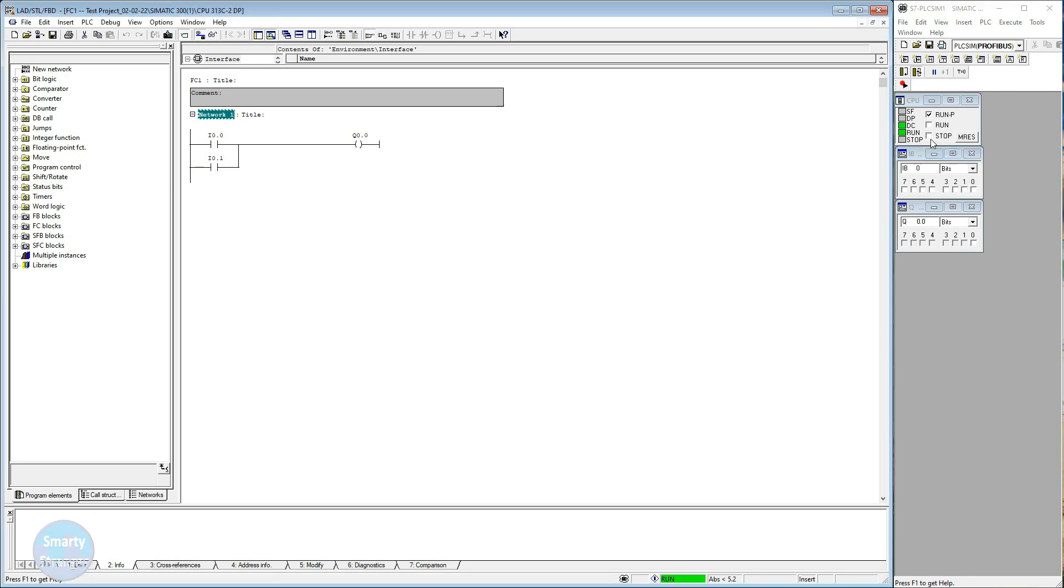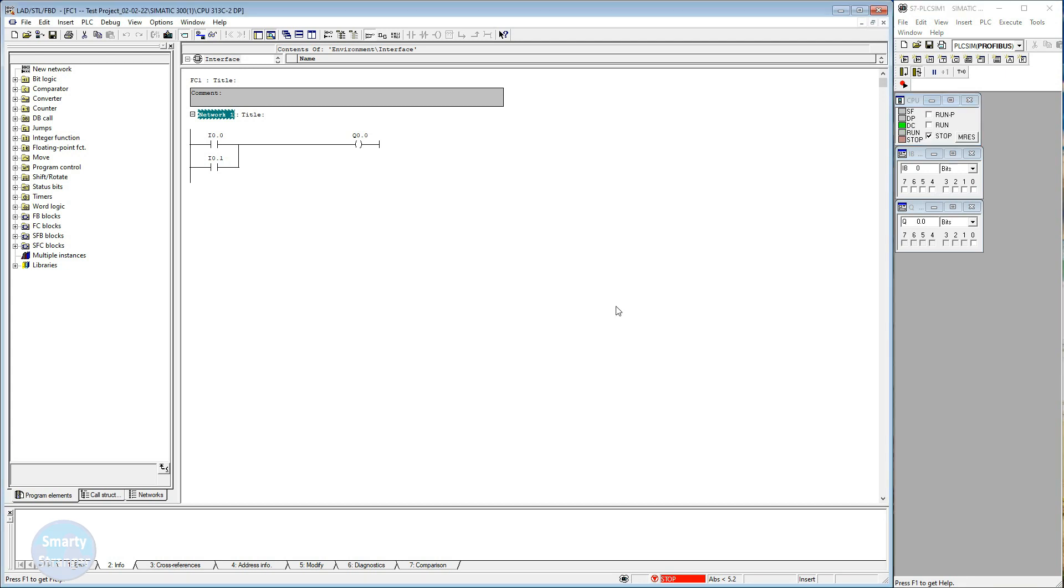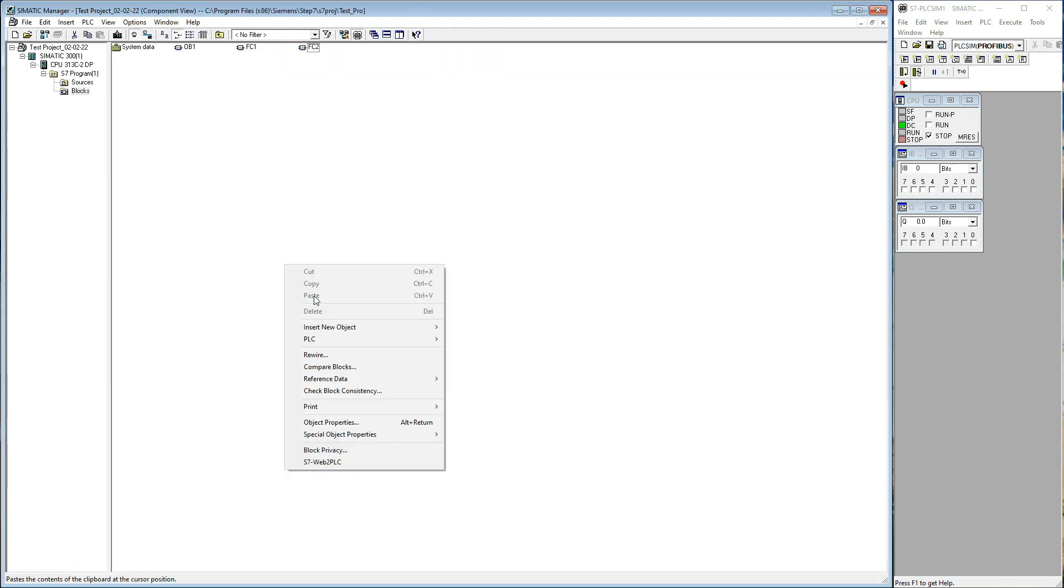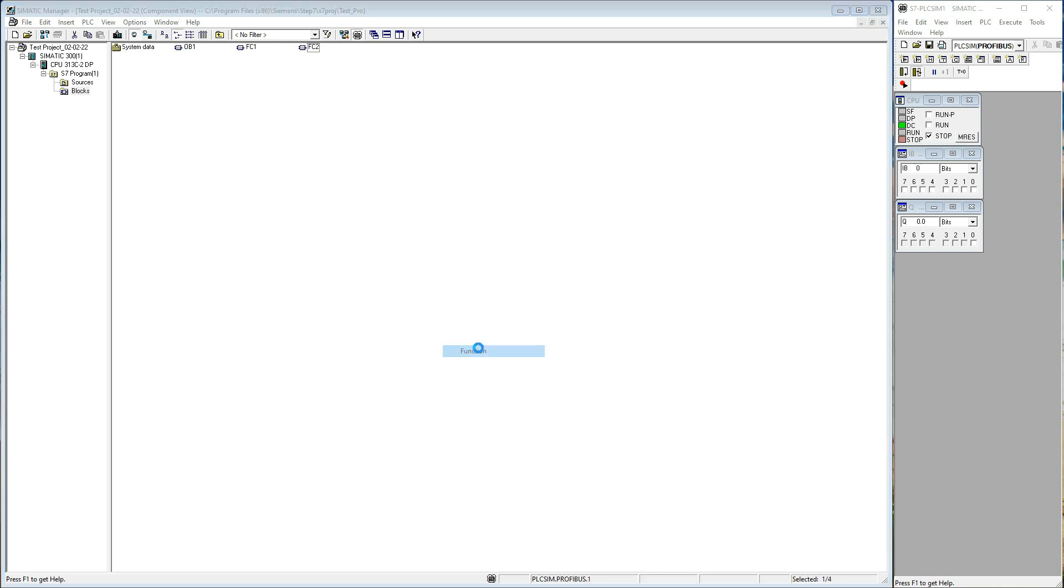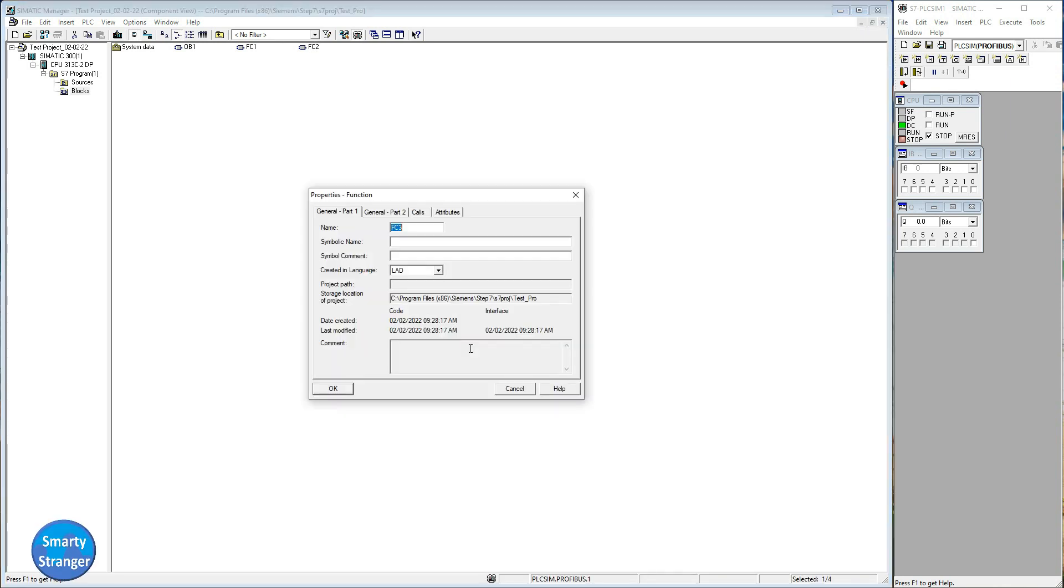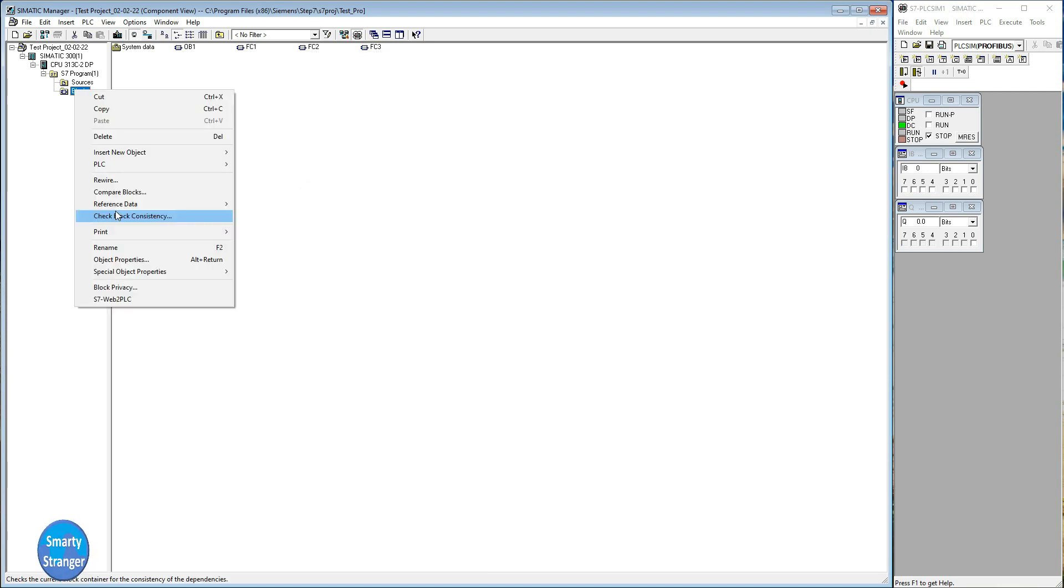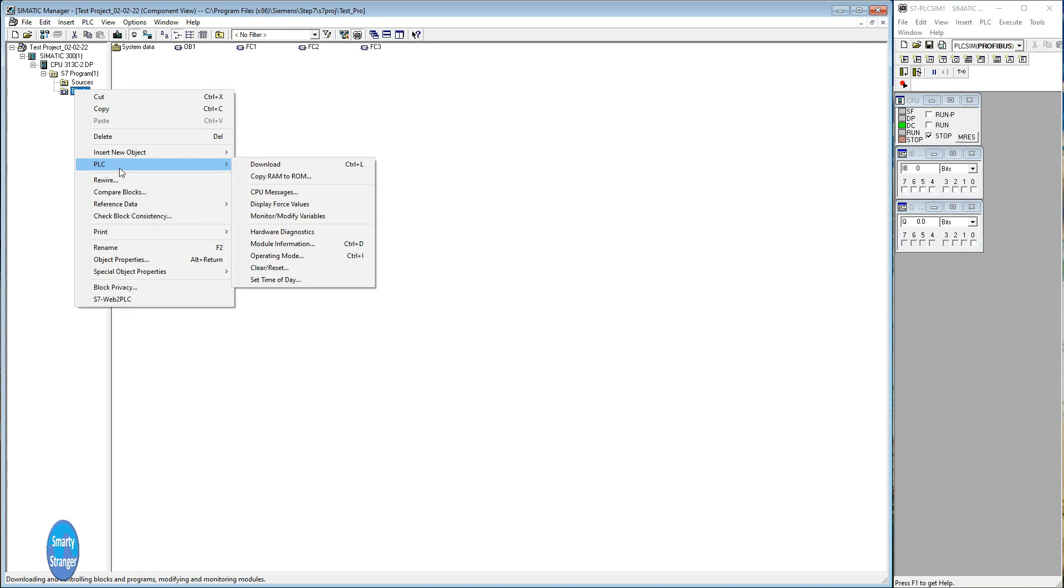OK, now we make some more FCs and download them into PLC. You can download complete program during process is not running, means in shutdown. When your process is running, avoid complete downloading, because during running when you try to download complete program, CPU will stop.